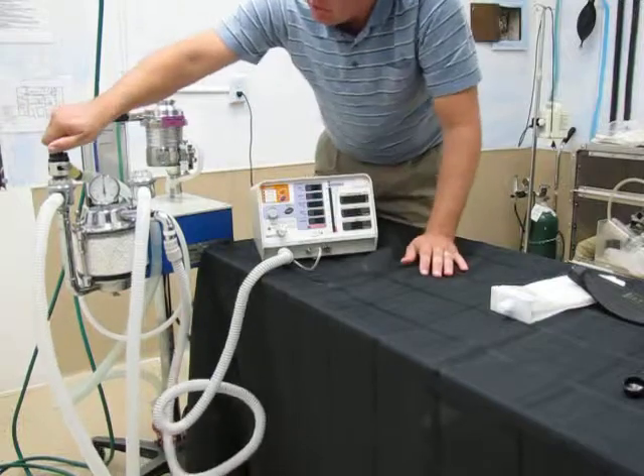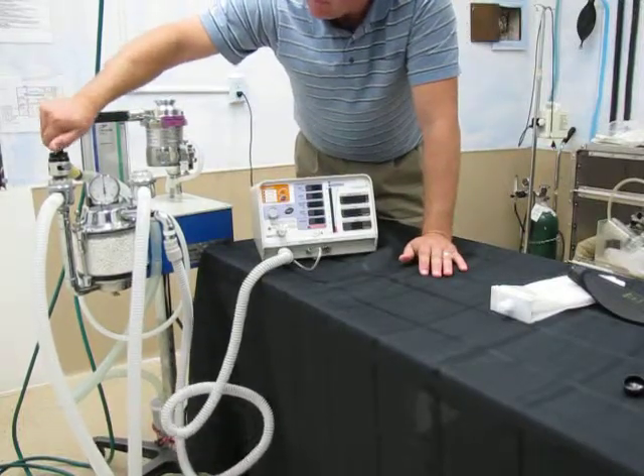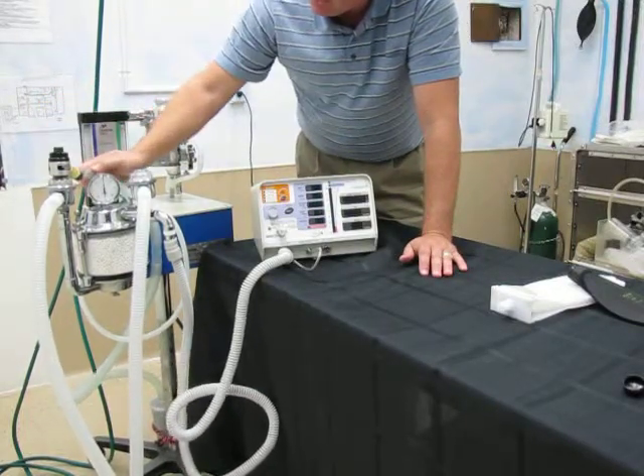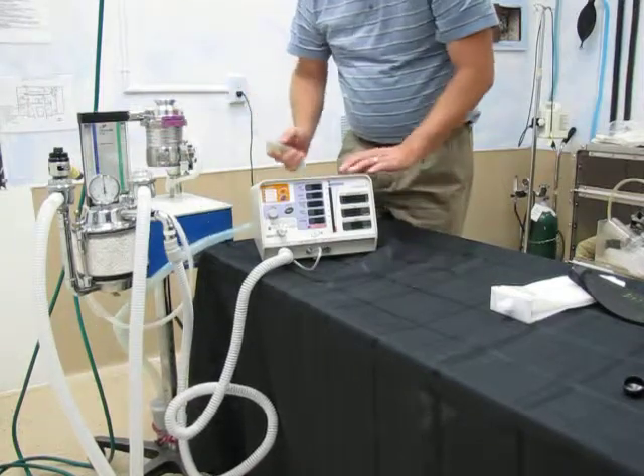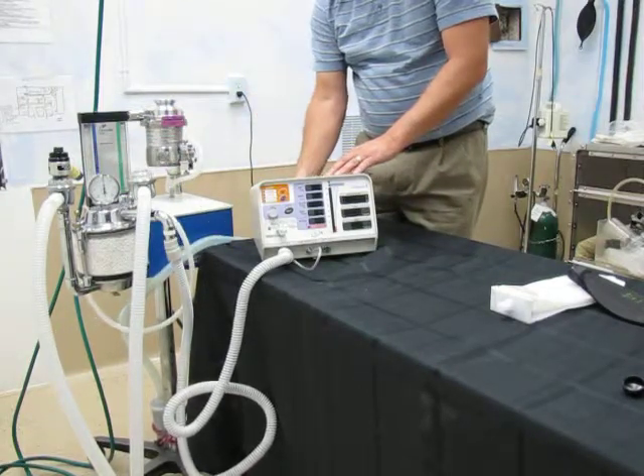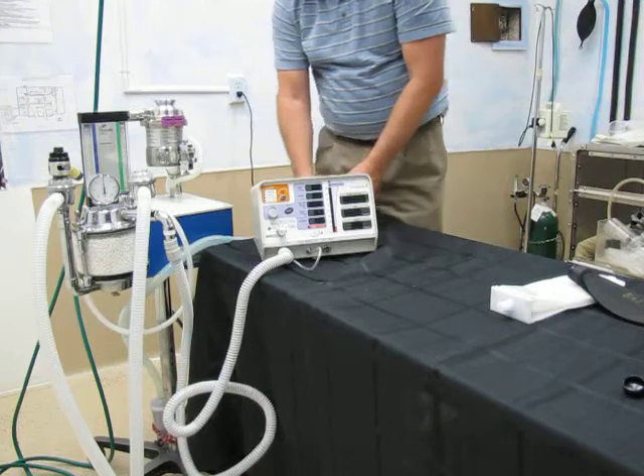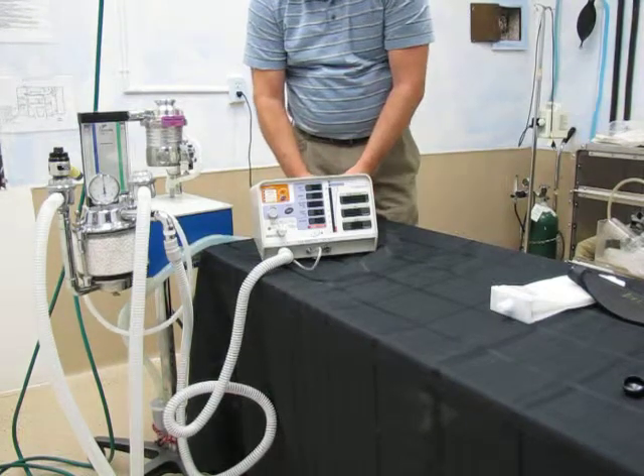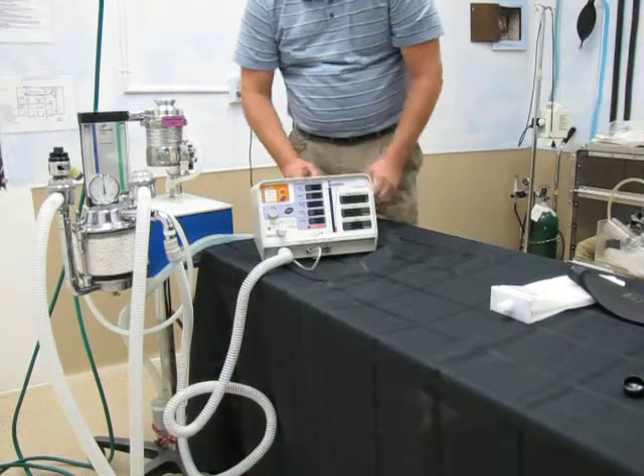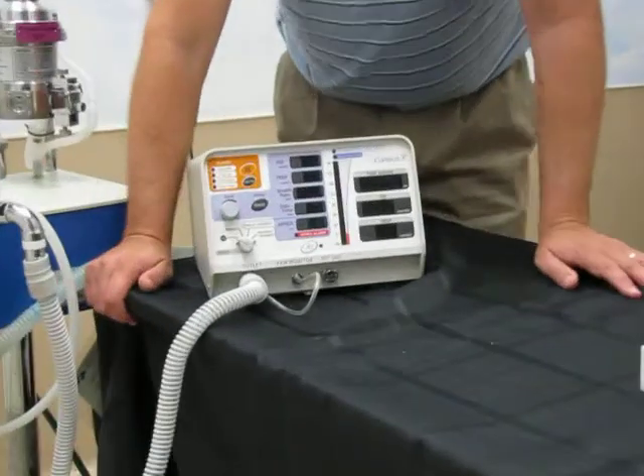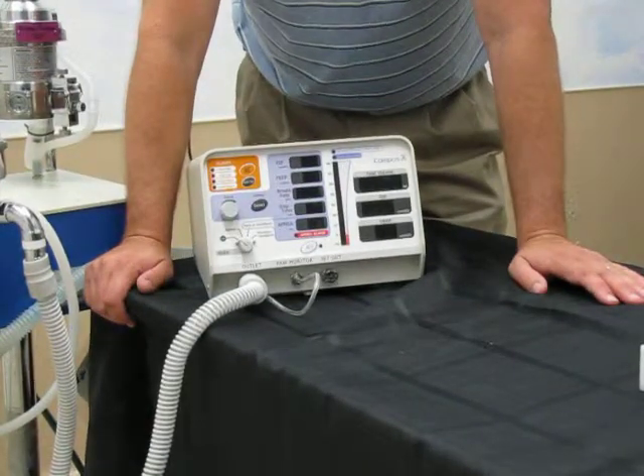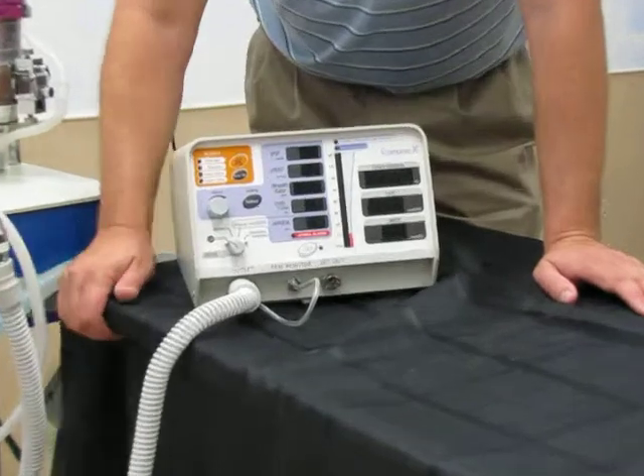And then we're going to close the pop-off valve and remove the scavenging hose from the back of the pop-off valve and hook it to the back of the ventilator at the scavenging exhaust port. And then at this point, we need to do a calibration of the volume in the circuit.